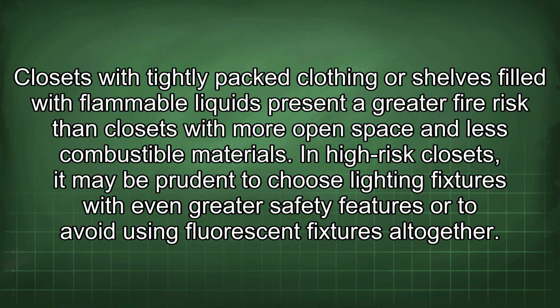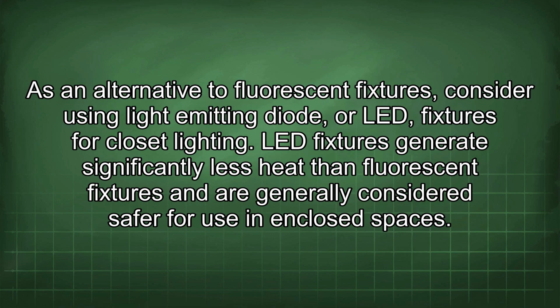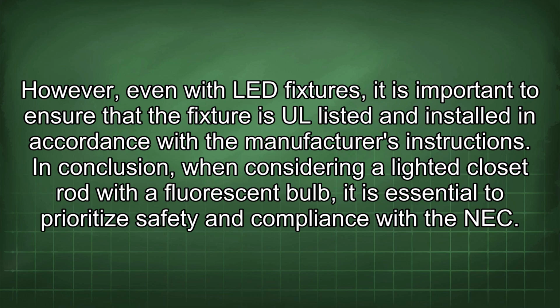In high-risk closets, it may be prudent to choose lighting fixtures with even greater safety features or to avoid using fluorescent fixtures altogether. As an alternative to fluorescent fixtures, consider using light-emitting diode, or LED, fixtures for closet lighting. LED fixtures generate significantly less heat than fluorescent fixtures and are generally considered safer for use in enclosed spaces.